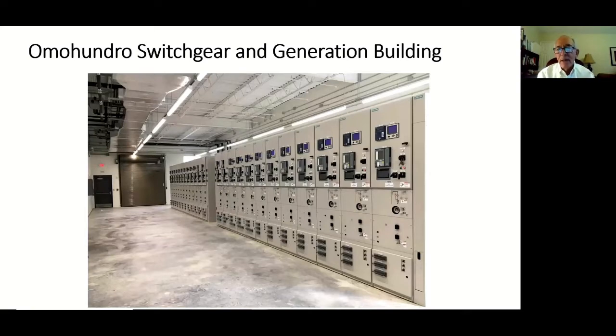Switchgear controls how we deliver power from that substation, and again this is a totally redundant system. The front half of these switchgear banks, down to the break in the middle, is redundant to the back half, giving us full capacity to use one side or the other depending on conditions or problems. Significantly, at some cost, all of these switchgear cabinets are gas charged, with a gas that eliminates the ability for arcing. That lets us get by with half the size of cabinet we'd otherwise need, making the building half the size it would have been with old traditional switchgear that wasn't gas charged. It's a real novel system.